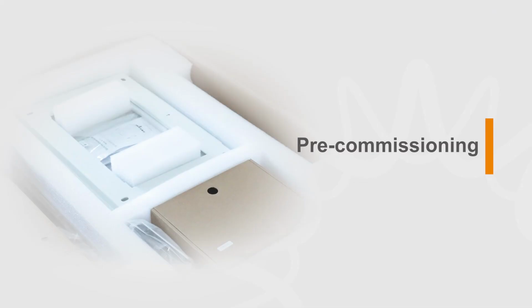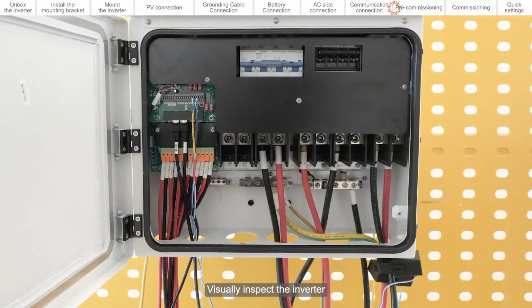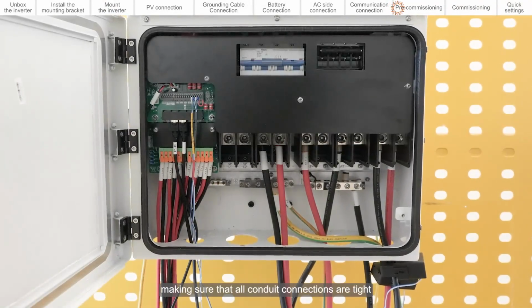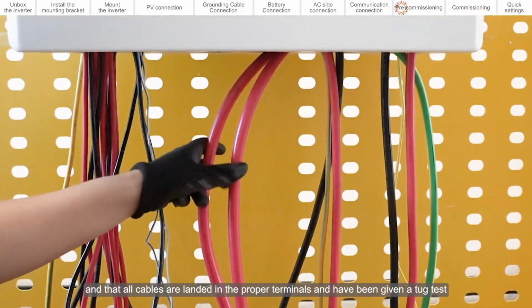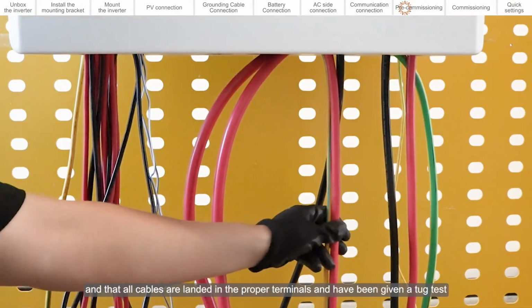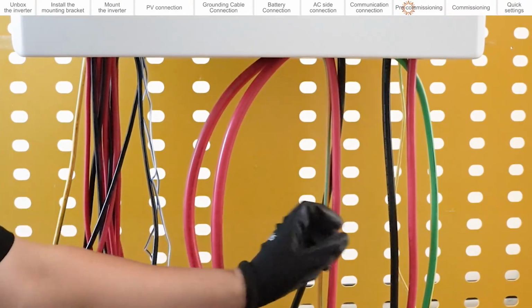Pre-commissioning. Visually inspect the inverter, making sure that all conduit connections are tight and that all cables are landed in the proper terminals and have been given a tug test.